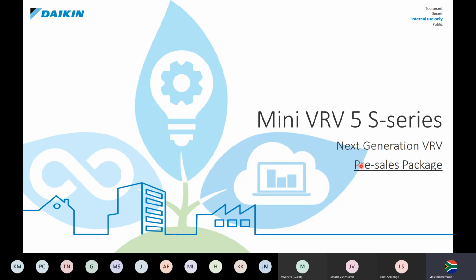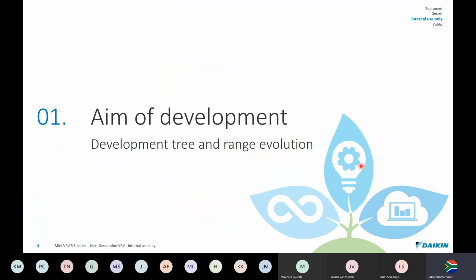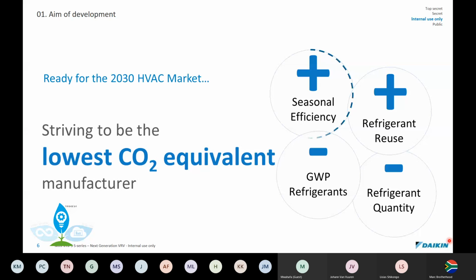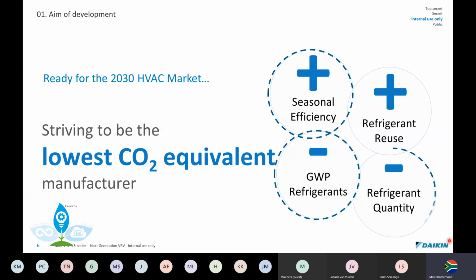Okay, so this will be the mini VRV5S series, which will be the next generation in VRV equipment. What is the aim of the development? Well, due to the Kigali agreement and amendment that has come into force with the phasing down, not phasing out, of R410A refrigerants, Daikin have already proactively developed R32 refrigerants. So they are already in preparation for the 2030 HVAC market, way ahead of any other manufacturers. And the objective is striving to have the lowest carbon dioxide equivalent for any possible refrigerant leaks.